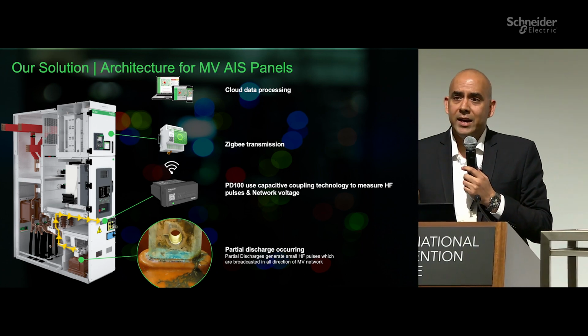Now, the whole idea is, why do we need to have continuous monitoring? And why do we need experts to do the processing? Again, partial discharges are quite complicated. You could have different kinds of curves. You could also have external mediums. Suppose you're doing a noise measurement. You could have a motor running in your system, or you could have a generator running in your system, and it could disturb the signal. So you need expert data processing and an expert to analyze the signals and tell you what's the noise and what's the actual issue which is happening.